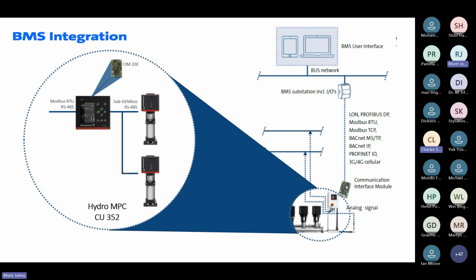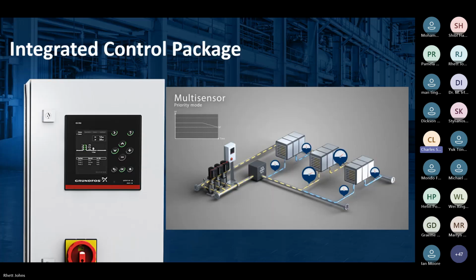Exactly. And that's the real beauty of coming to a company where I was predominantly only focused on the selection of pumps. For a pump supplier, pump control was something we were never really exposed to, because it wasn't part of our scope. So seeing the type of systems that Rhett's presenting underlines the earlier point about the importance of designing a system where you're taking everything into control, and that is obviously the system loads. You really need to have that information when you're sizing your pumps. Having controls that are working autonomously, after only ever seeing one small part of the puzzle, really underlines the value this will bring to an efficient system. Yeah. Sorry, Rhett.